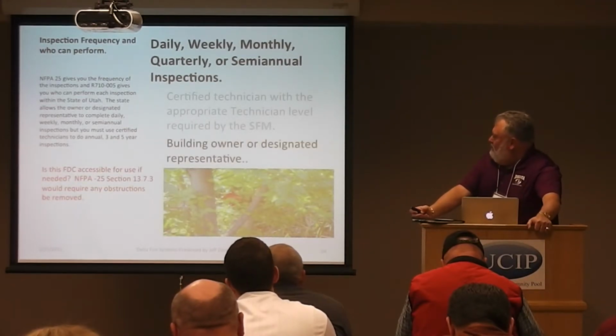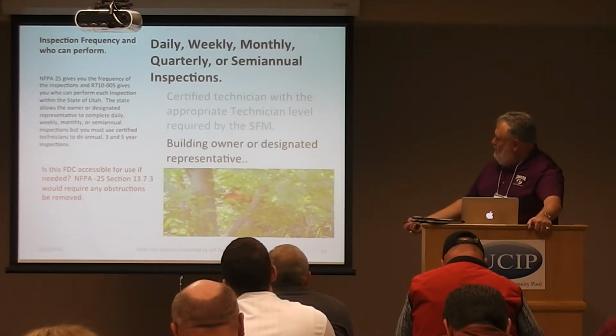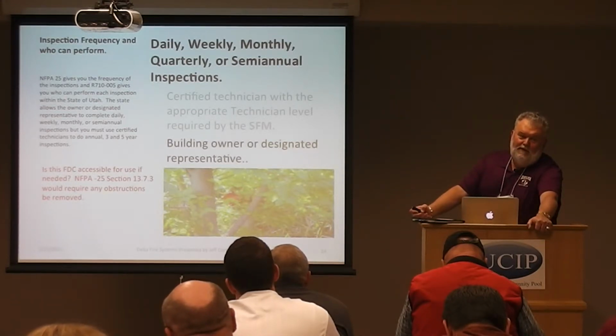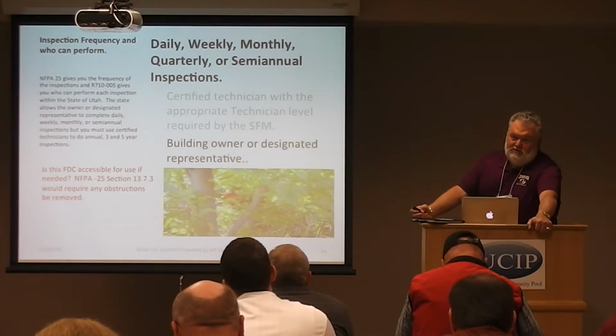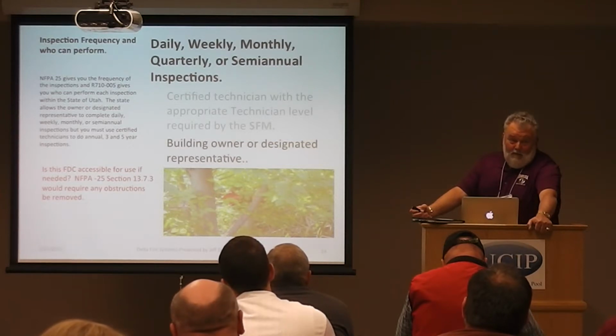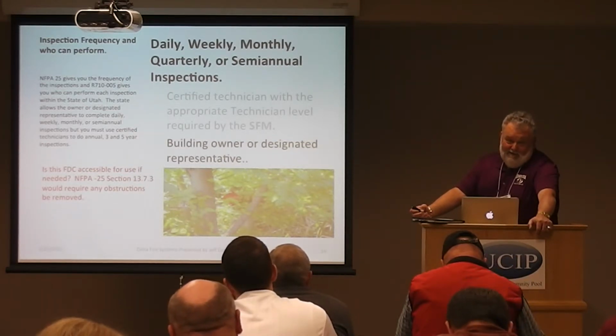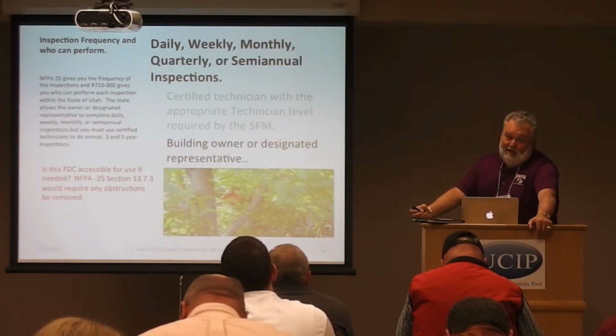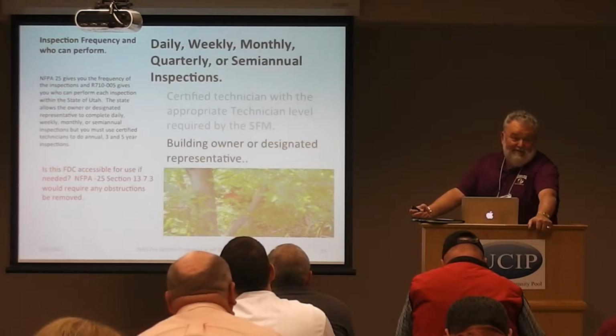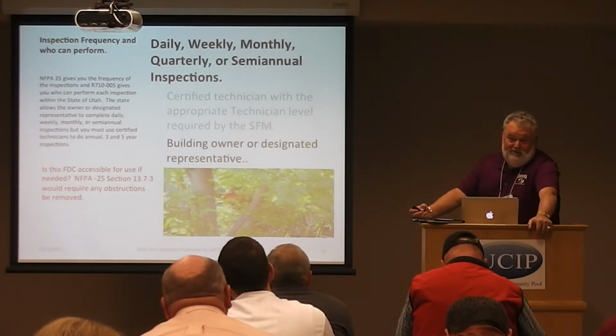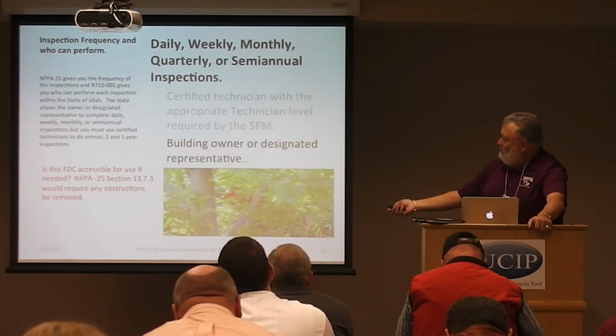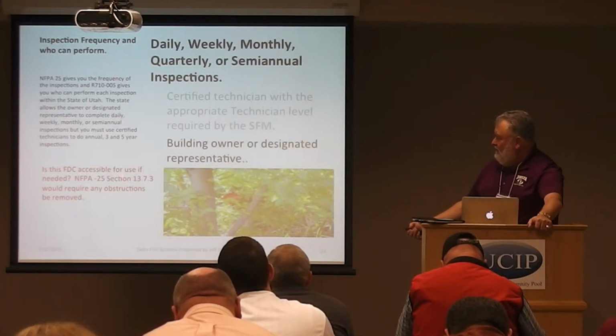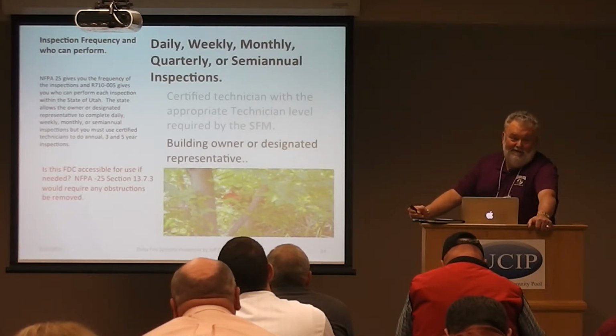And here's what the building owner or designated representative can do daily, weekly, or monthly. I don't know if you can see this, but right there, that's a freestanding fire department connection. And I'm sure that fire department connection was installed when there were no trees there. The fire department probably wouldn't find it in the event of a fire, and second of all, I don't think they take the time to cut trees down to get to it. So, in essence, you're just tying the arm of the fire department at that point. Anytime you see something like that, and this section's very clear, that tree should be removed.